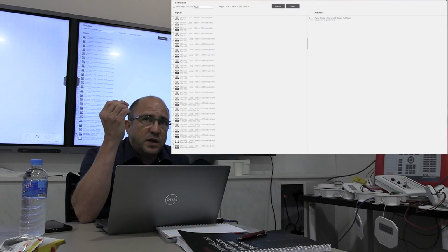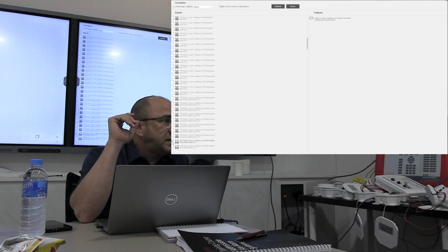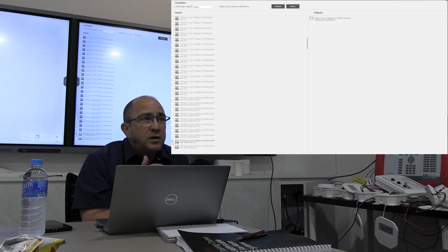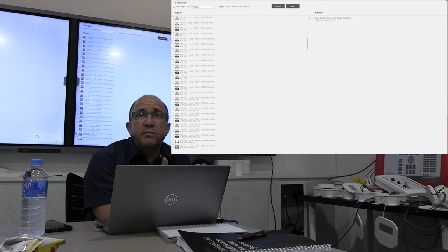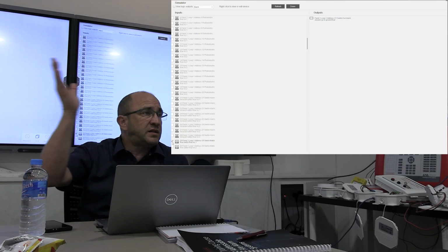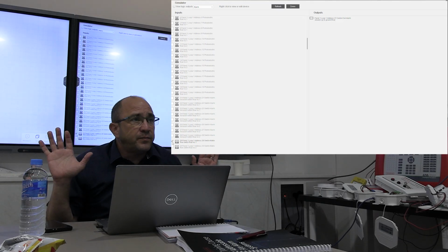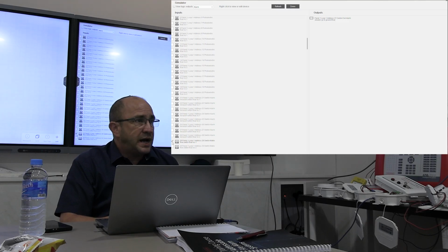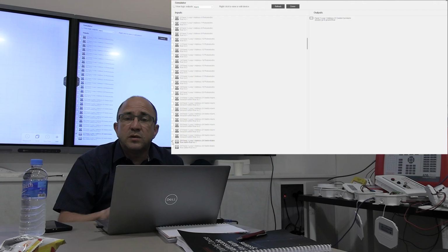Now if you add another section with 17 more detectors, all you have to do in order for the elevator to go down, you must ask which floor are them. They are floor number 2. I go to zone number 2, I add those 17 detectors and finish programming. I don't have to touch anything. The elevator, I promise you, will go down. I don't have to go inside the outputs. Everything automatically will work. Did you want to say something? Yes, sorry. This is one of our advantages.